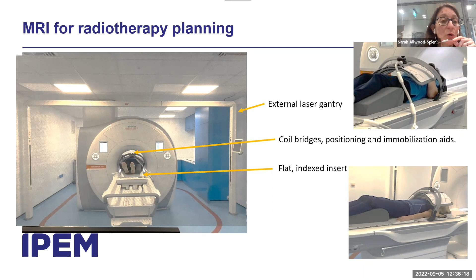The first thing we learn in MRI safety is that our superconducting magnet is always on. It's ramped up at commissioning, and provided there's enough helium to keep it cool, it will remain on until it's decommissioned 10 years or so later. So even if the power is off to the hospital, your main magnetic field is still on.